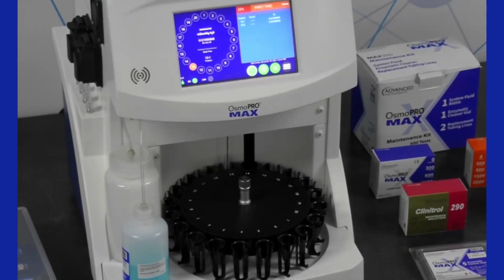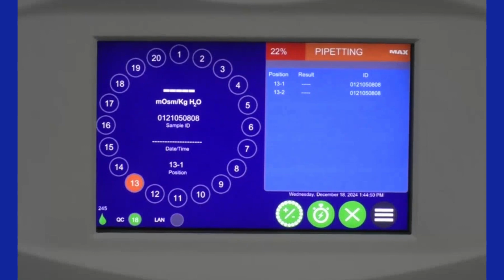Okay, so pop back to the software here. You can see the little progress bar up there. It says it's pipetting. It's taking the sample up, and then it will say testing once it proceeds to the testing phase of the entire test duration, which takes about 4.5 to 5 minutes. But you'll be loading multiple tubes on this instrument all at once and be able to walk away, and that LIS will communicate everything over into the system that needs to be communicated once the test completes, left there for you to verify, depending on how you have your LIS set up.